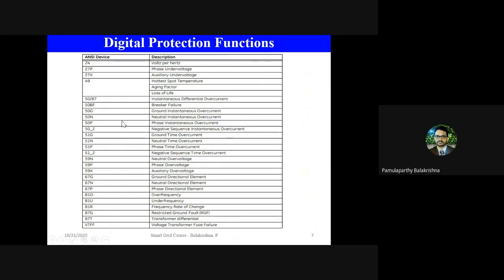Yeah. So, see, 61850 is majorly related to how we further standardize the data within the protection function. So, for example, these protection standards were there for a long time, and they were being implemented for a long time, whereas 61850 came into existence in the last 10 years, and now it is becoming more standardized for digital substation. So what 61850 does is it takes this particular standard where they will mention, let's say for example, volts per hertz is the protection function. So it requires voltage and it requires frequency in order to execute.